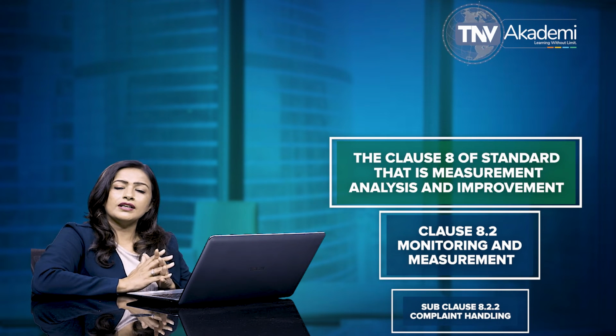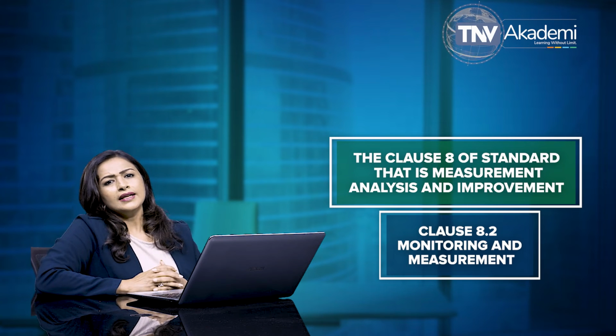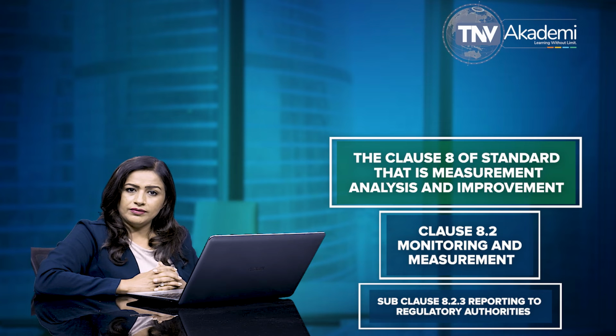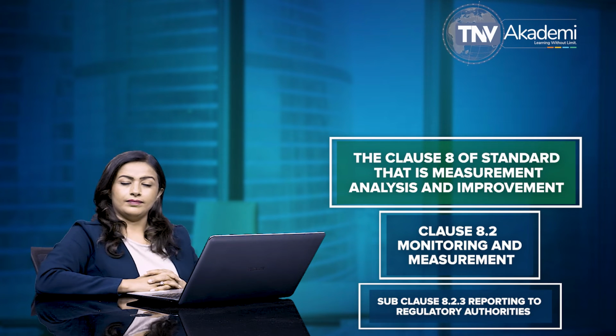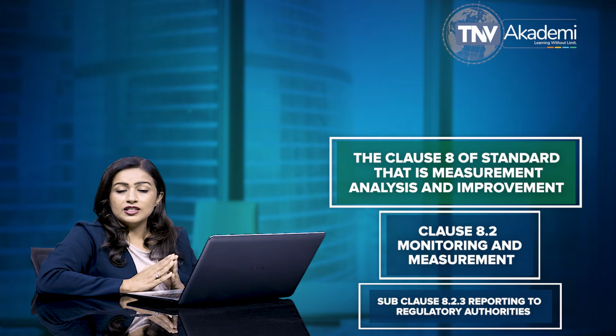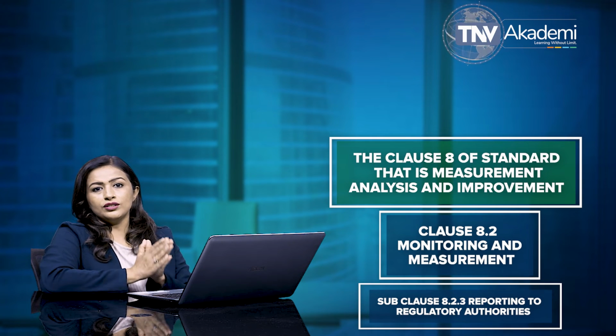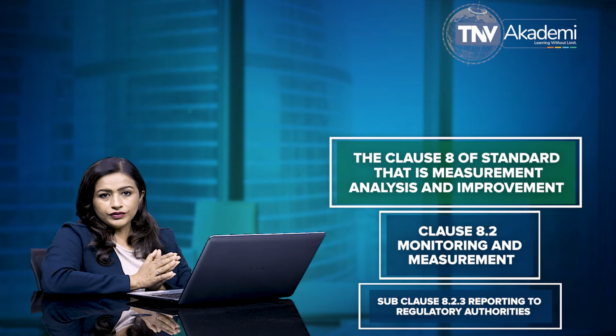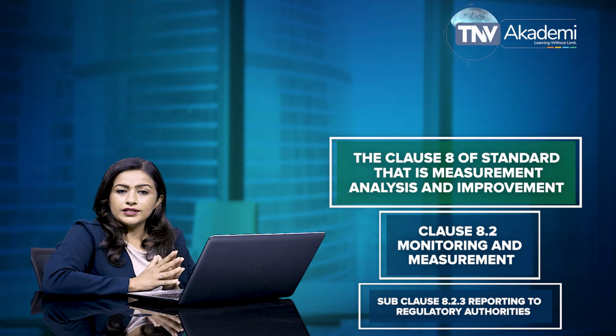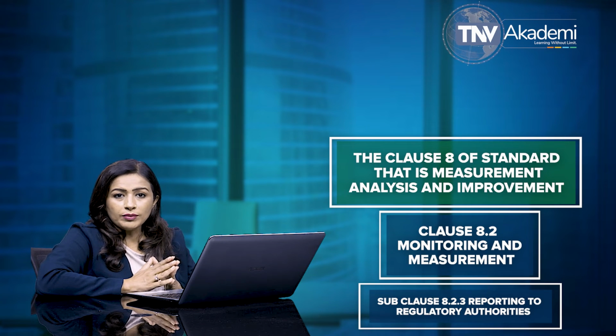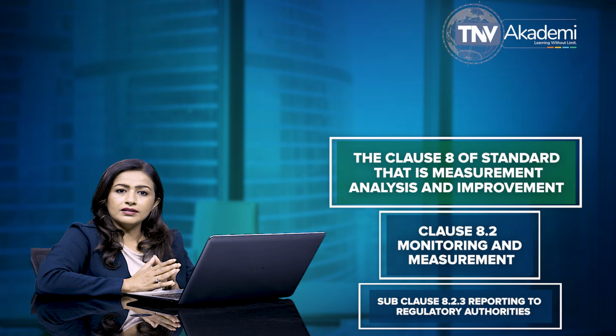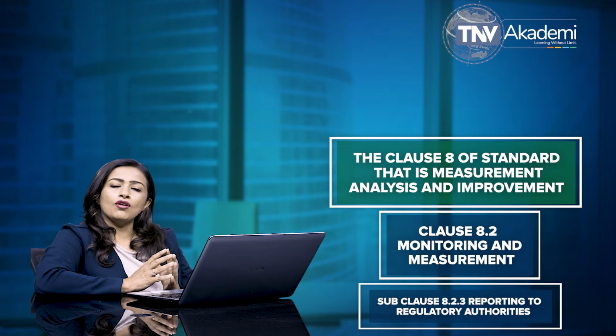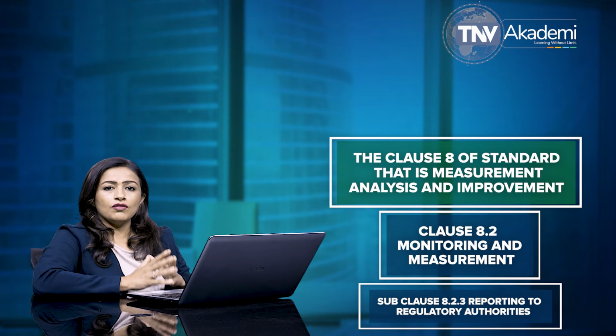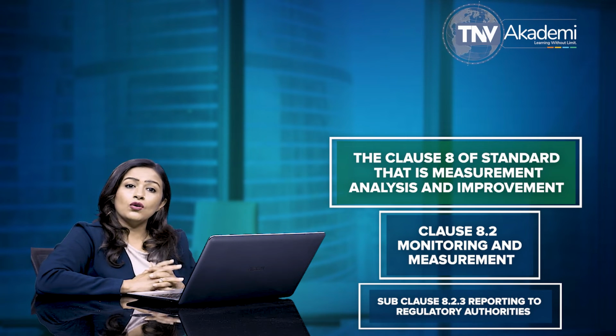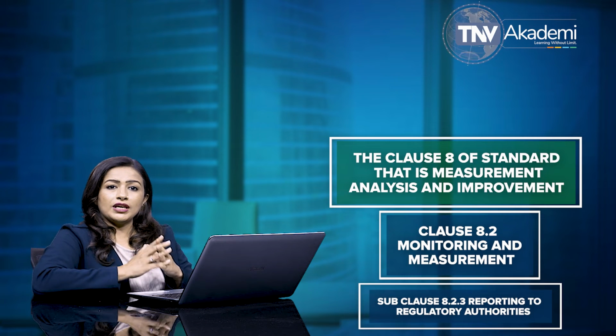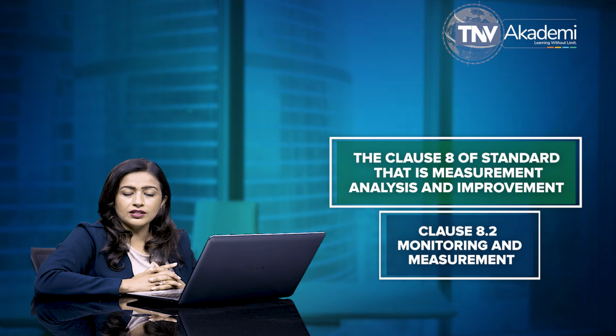ISO 13485:2016. Let me discuss now the subclause 8.2.3, reporting to regulatory authorities. This subclause 8.2.3 specifies that the organization is required to document procedures for providing notification to the appropriate regulatory authorities, if applicable regulatory requirements require notification of complaints that meet specified reporting criteria of adverse events or issuance of advisory notices. Further, according to this clause, records of reporting to regulatory authorities are required to be maintained by the organization.